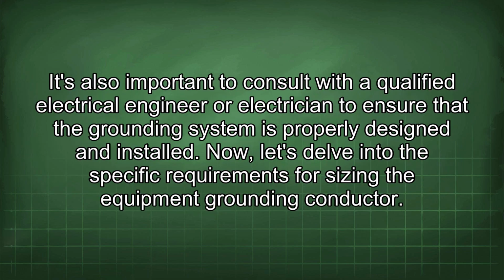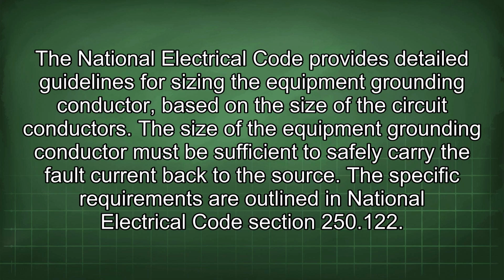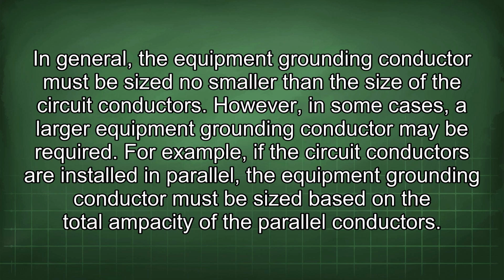It's also important to consult with a qualified electrical engineer or electrician to ensure that the grounding system is properly designed and installed. Now, let's delve into the specific requirements for sizing the equipment grounding conductor. The National Electrical Code provides detailed guidelines for sizing the equipment grounding conductor based on the size of the circuit conductors. The size of the equipment grounding conductor must be sufficient to safely carry the fault current back to the source. The specific requirements are outlined in National Electrical Code Section 250.122.